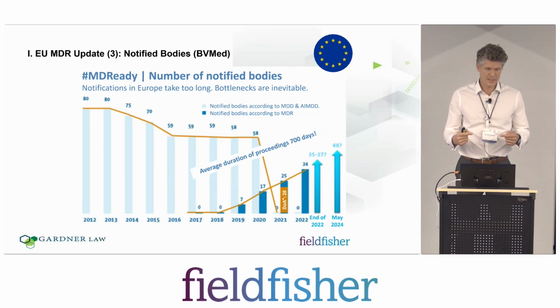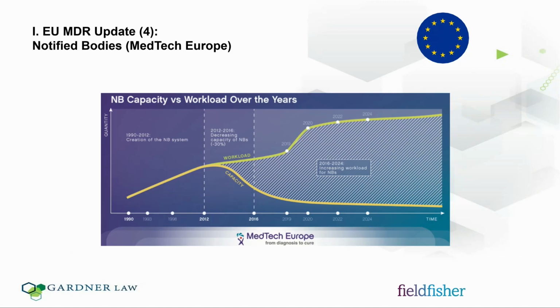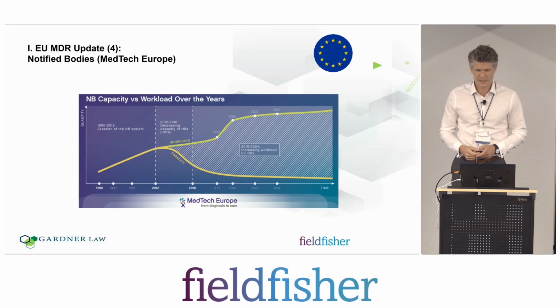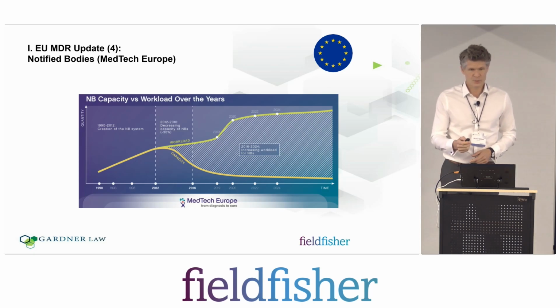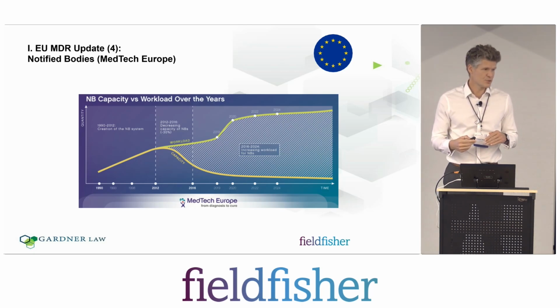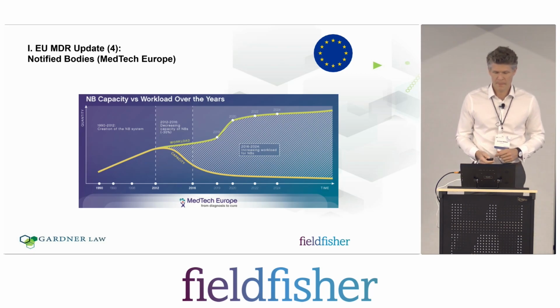So this is a table that was drafted by the German BVMed, and now I'll show you a slide of MedTech Europe, where you can see that not only does the number of notified bodies go down, but also the workload goes extremely up. I'm just telling you that a conformity assessment procedure under the MDD required checking whether a medical device is in compliance with 17 articles, and now it's 127 articles. So the capacity and the workload, there is a huge gap between both of these scales.